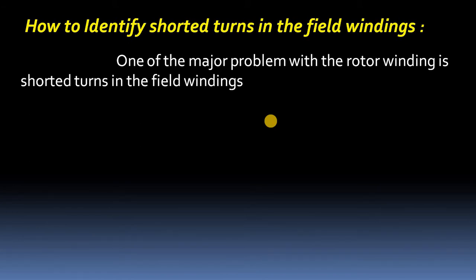Another reason for shorted turns is contamination. For large generators or large synchronous motors, bearings need cooling, which can be arranged using lubricating oil or water. These water or oil particles will contaminate the rotor field poles, causing shorted turns.